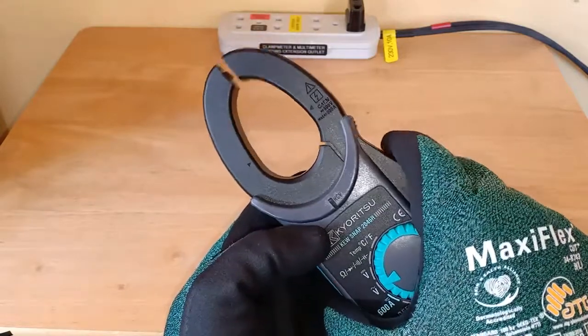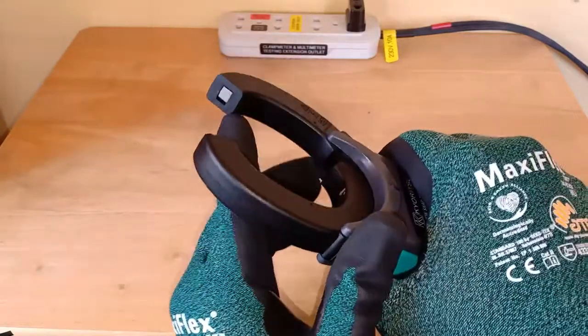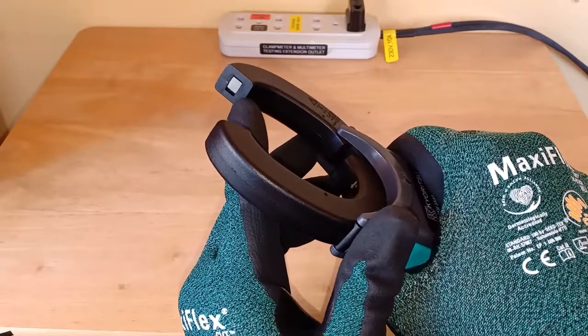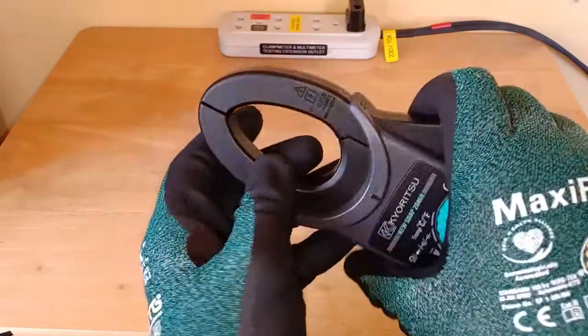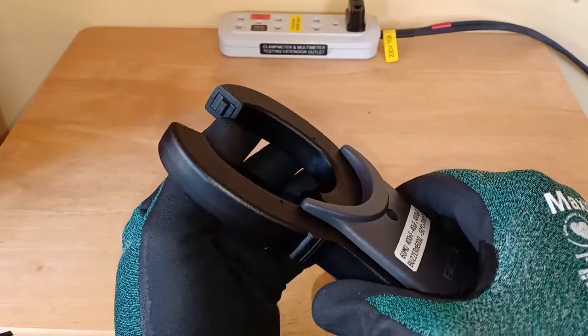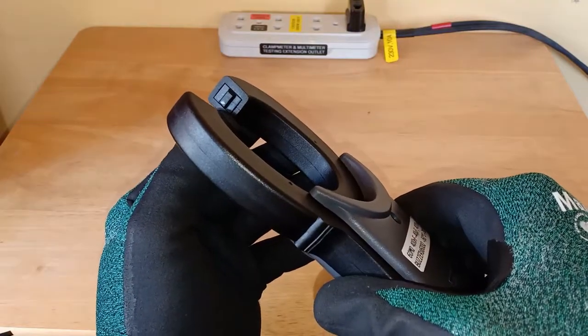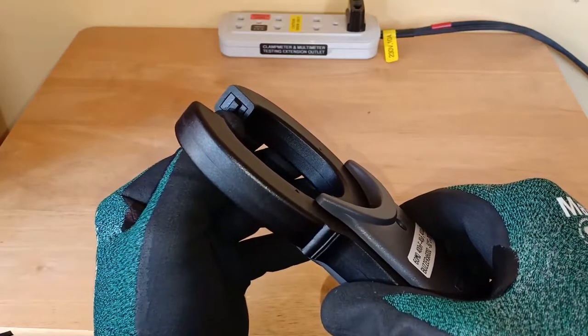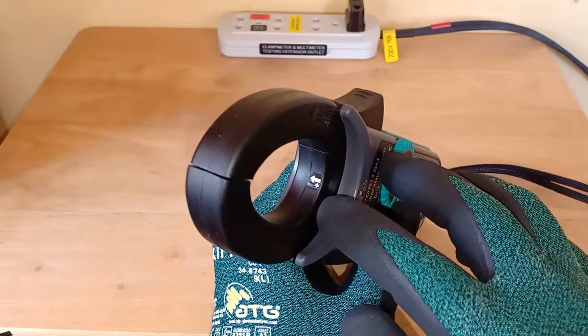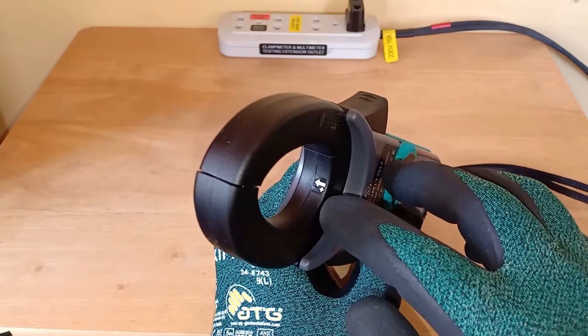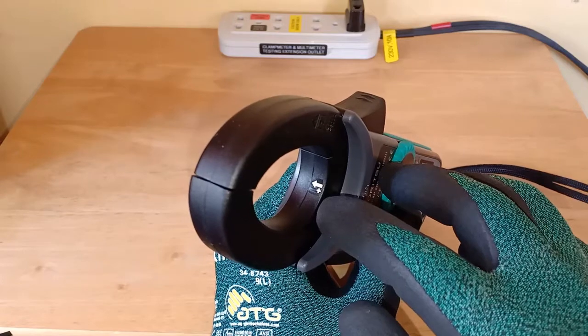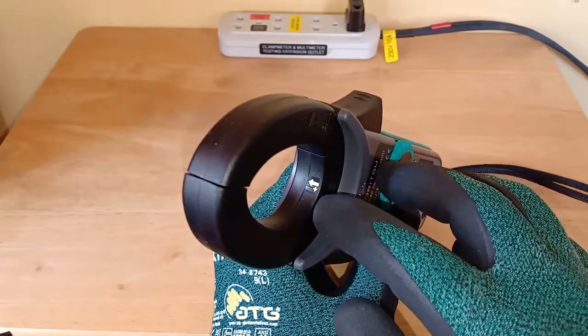Only one part is movable. One end has the metallic part exposed, while the other end is insulated. The instrument's Hall effect sensor is located here. There is also an arrow and plus sign at the bottom part of the jaws to provide guidance when using the clamp meter to measure DC current.